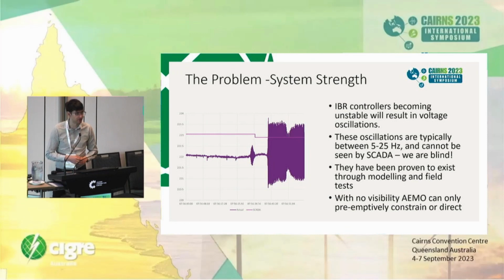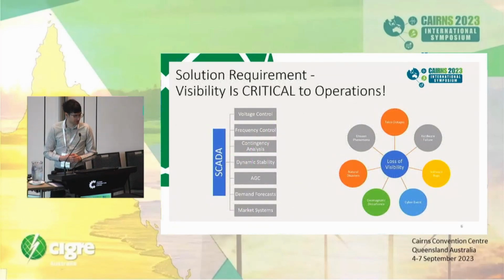The oscillations have been proven to exist through extensive simulations, modelling, and fault recorder measurements. So we know they're there, but we have absolutely no visibility. And I probably don't need to be the one to tell you, but visibility really is critical to operating the power system. Our SCADA system feeds into so many services, and if the SCADA system isn't working or isn't up to requirement, then we have a serious challenge managing the power system. There are many reasons why the SCADA system might fail, but the one that's most concerning is probably this one here, the unseen phenomena. So not being able to see the issues. We just don't know what we don't know.